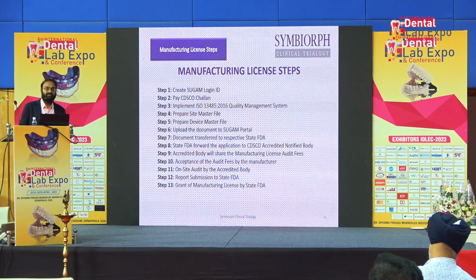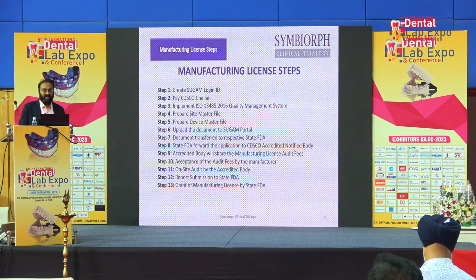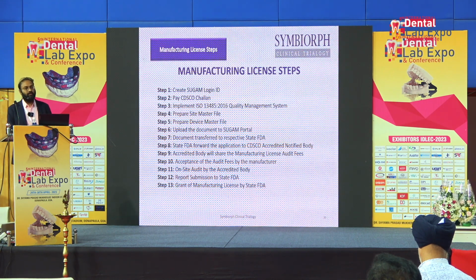Then step number 4 is prepare the site master file as per Annexure 1. Step number 5 is prepare the device master file as per Annexure 2 of the Indian Medical Device Rules. Once all these documents are prepared, you have to upload them to the SUGAM portal online. So everything will be done online. Once the documents are uploaded to the SUGAM portal, they will get transferred automatically to the state FDA.